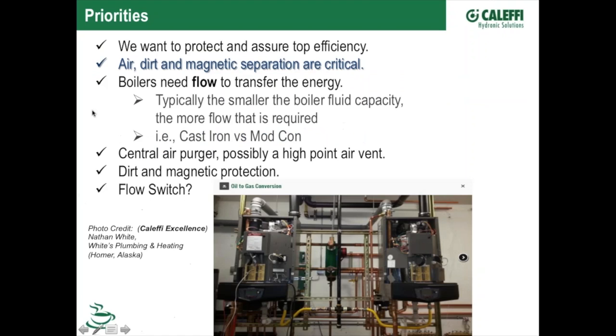Priorities, this is what we need to have in every system. We've got to make sure if we're selling our customers high efficiency equipment that we install it in a way, with the right components in the right place, that we provide that efficiency. If you're selling a 90 plus efficient boiler and you're putting it in with the wrong devices, or you're not getting the air or the dirt or the debris out of that, you're not in fact getting that efficiency that you promised or that you sold the person.